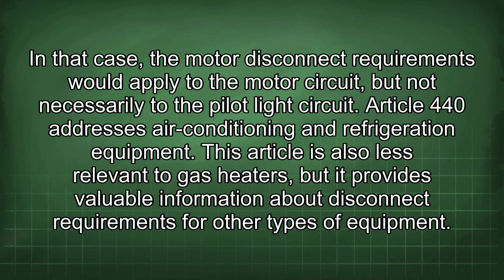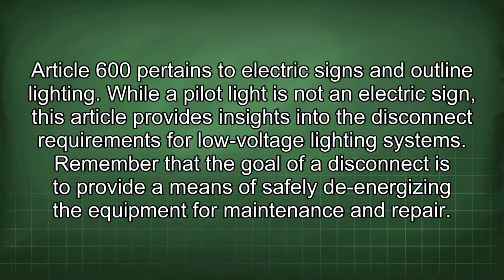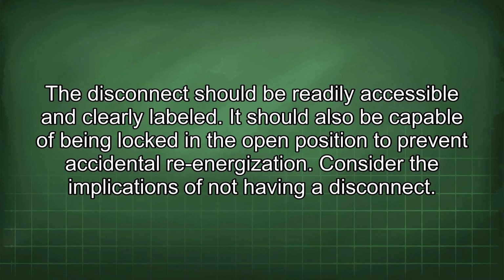Article 440 addresses air conditioning and refrigeration equipment. This article is also less relevant to gas heaters, but it provides valuable information about disconnect requirements for other types of equipment. Article 600 pertains to electric signs and outline lighting. While a pilot light is not an electric sign, this article provides insights into the disconnect requirements for low-voltage lighting systems. Remember that the goal of a disconnect is to provide a means of safely de-energizing the equipment for maintenance and repair. The disconnect should be readily accessible and clearly labeled. It should also be capable of being locked in the open position to prevent accidental re-energization.